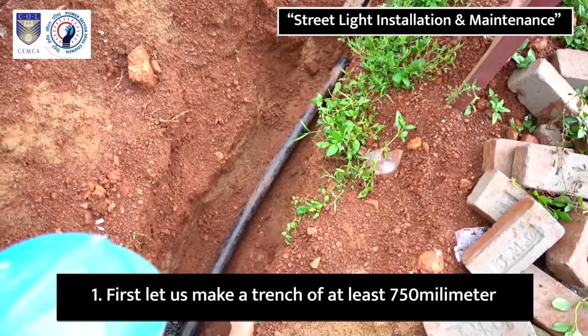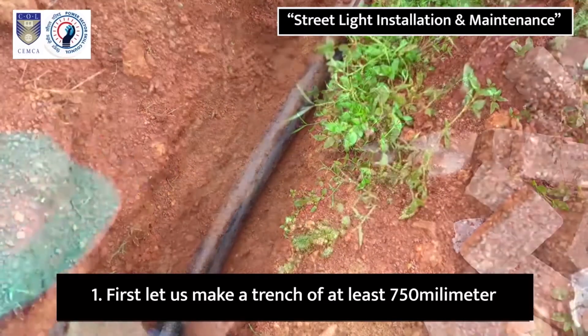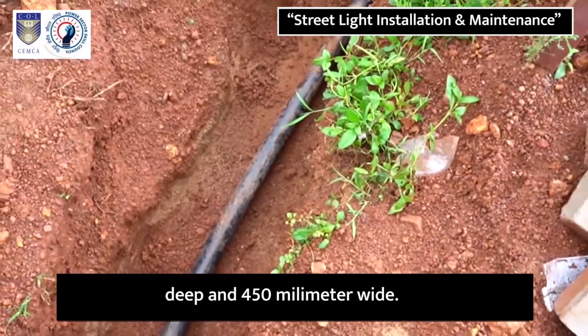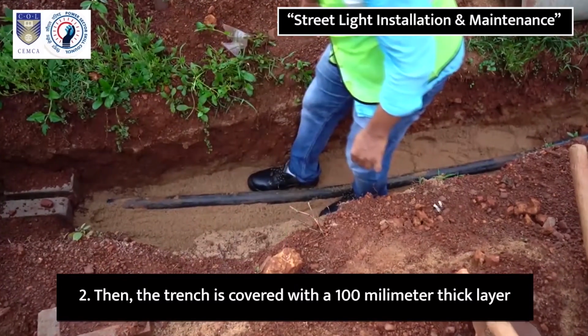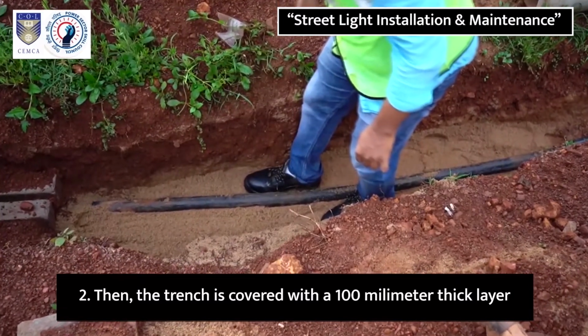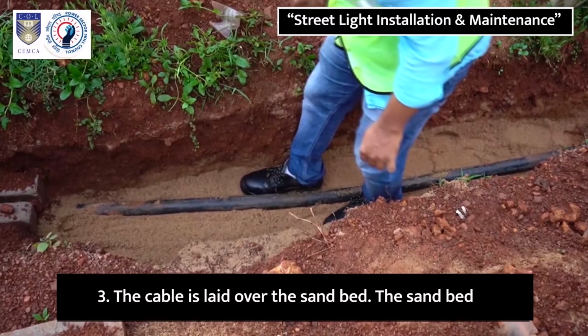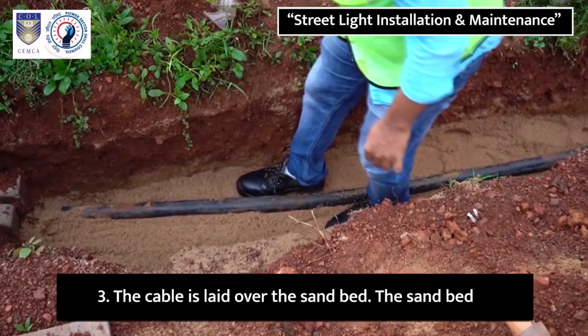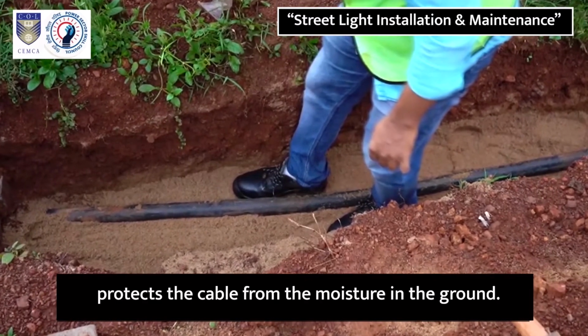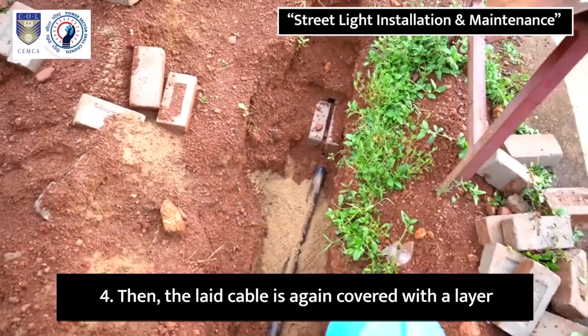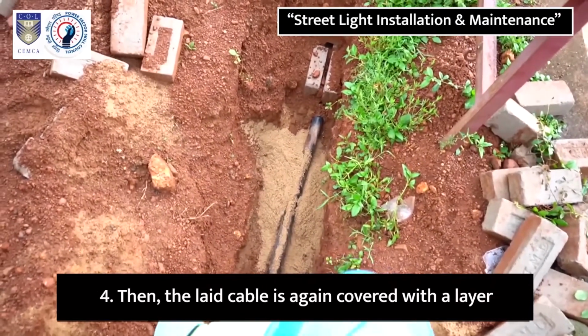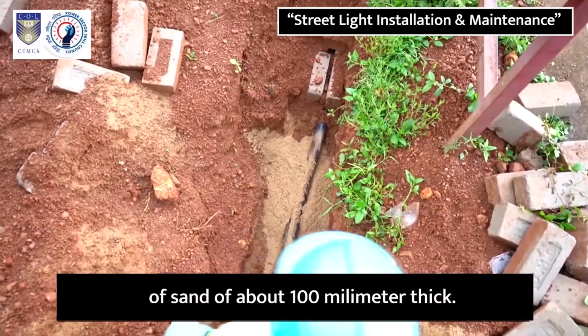First, let us make a trench of at least 750 mm deep and 450 mm wide. 2. Then the trench is covered with a 100 mm thick layer of fine sand. 3. The cable is laid over the sand bed. The sand bed protects the cable from the moisture in the ground. 4. Then the laid cable is again covered with a layer of sand of about 100 mm thick.